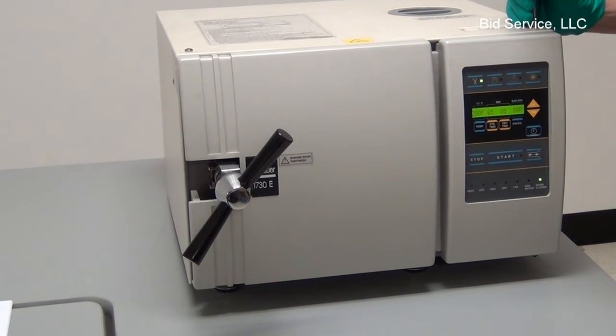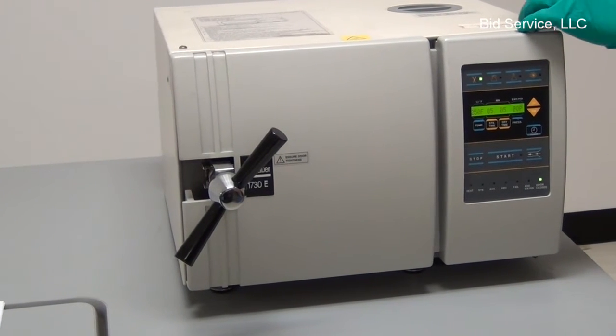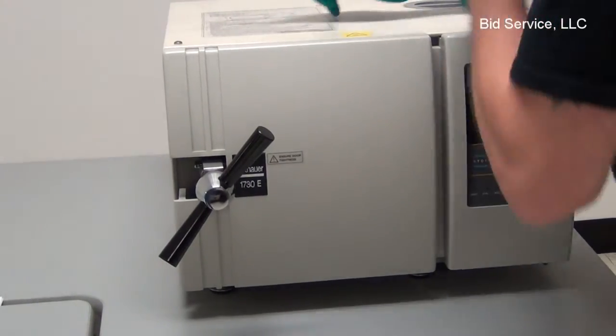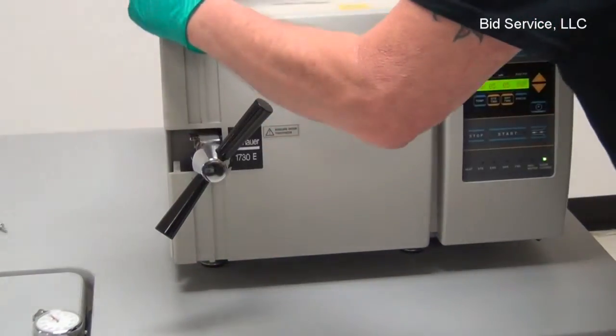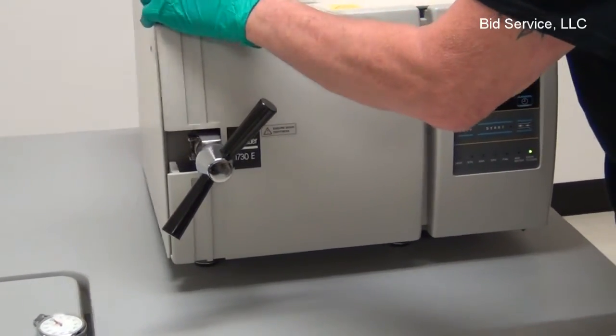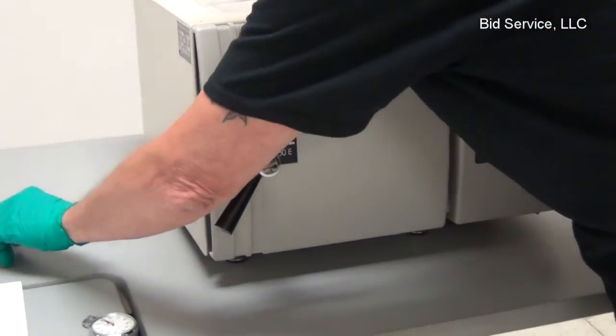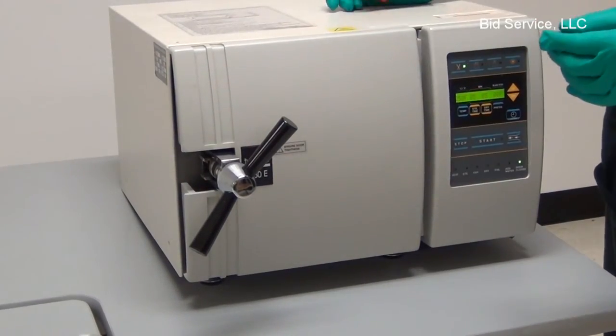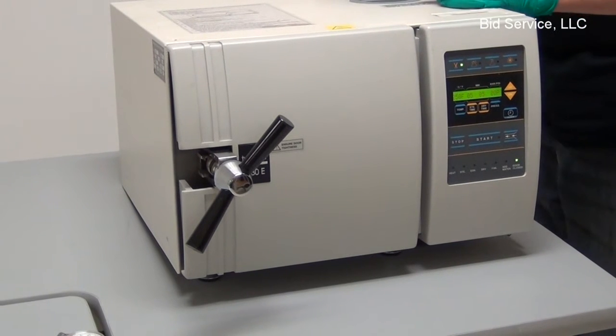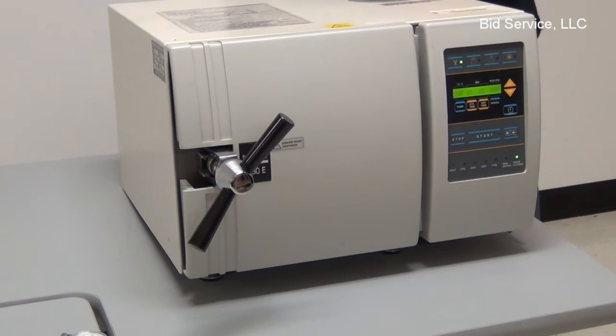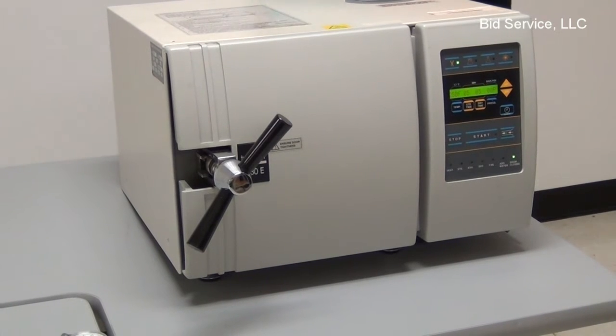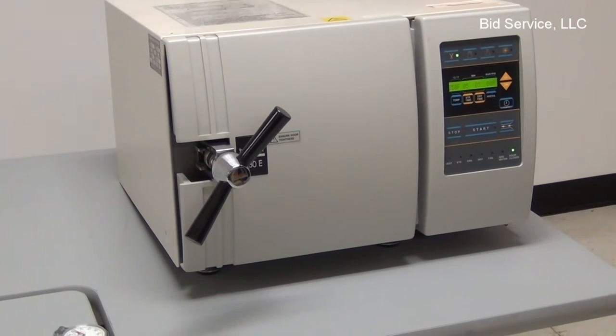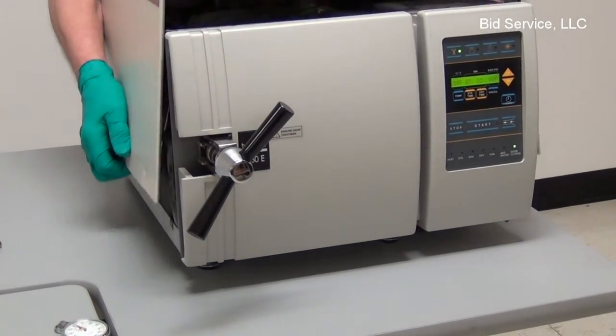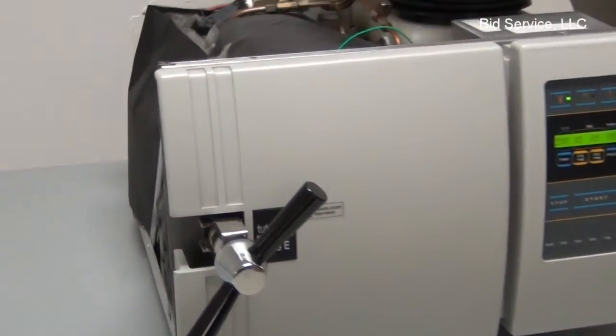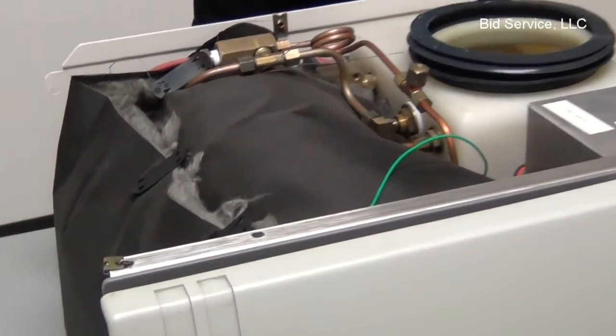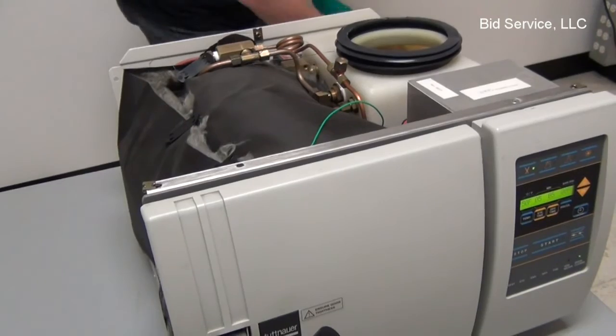If you take off the cover, and this is right in the book here, they say the most common thing that can happen is that there is an air jet. And if that air jet is not periodically cleaned, it'll result in a failure of spore testing. If you were to have a spore testing strip inside, it may not change color as it's supposed to. So even though this is periodically checked by maintenance personnel, it is important that even the operator, who might alert the maintenance personnel, be aware of this very simple little maintenance thing. It's very important.